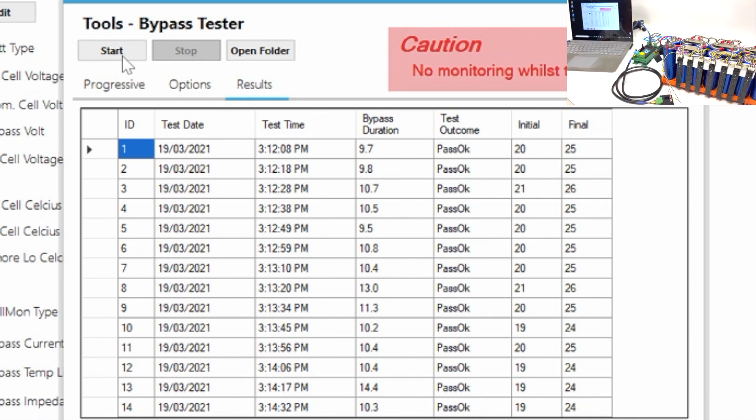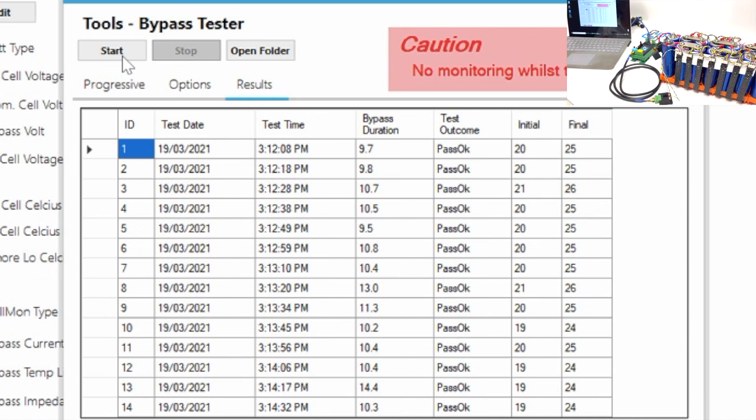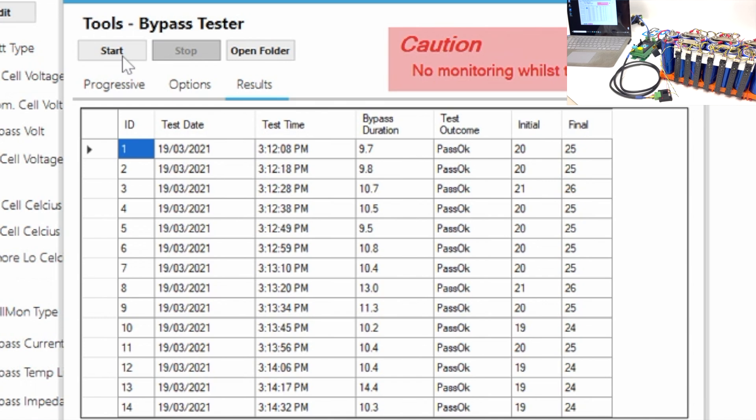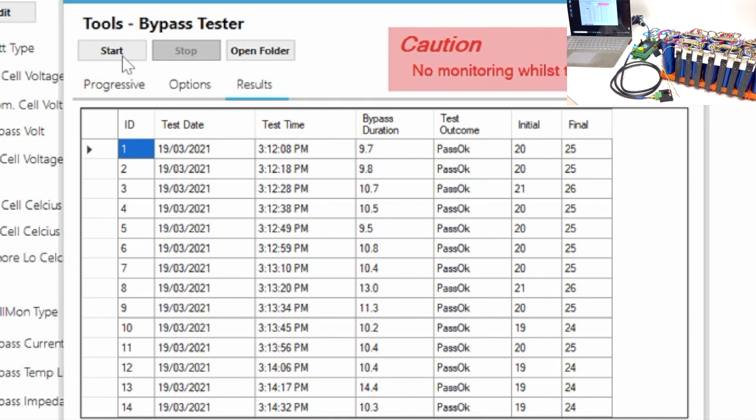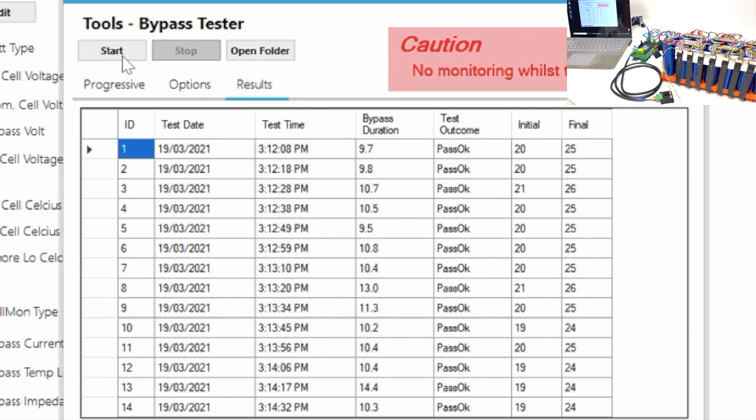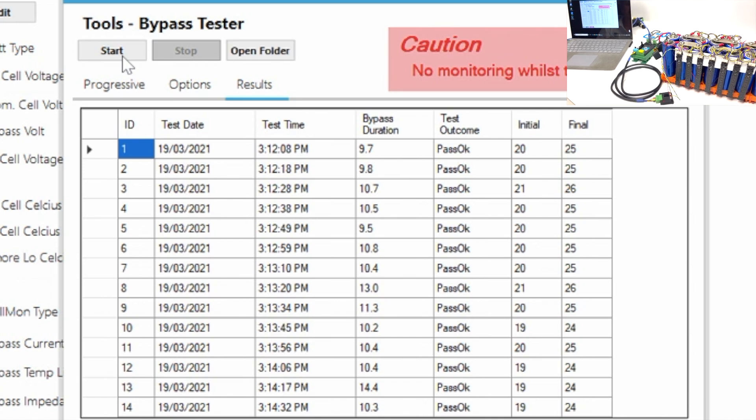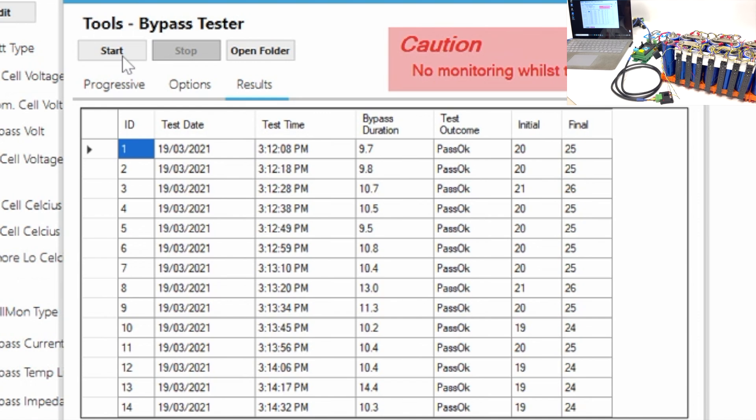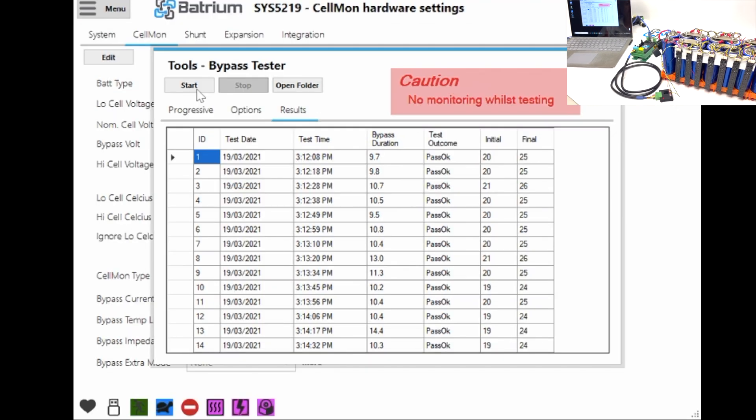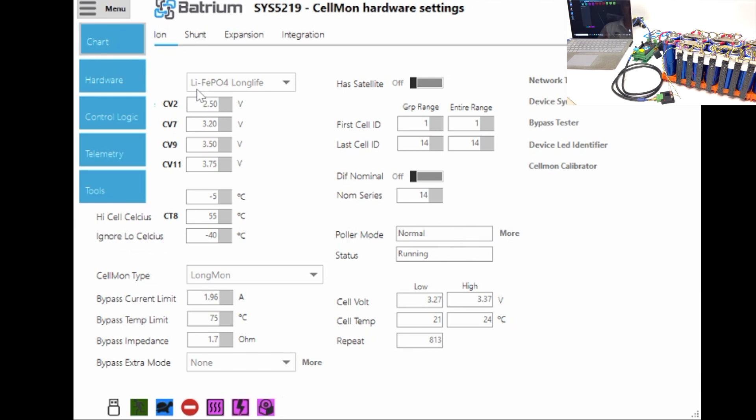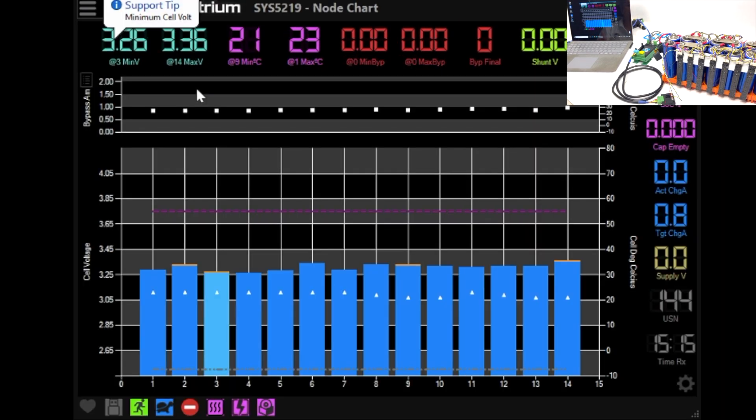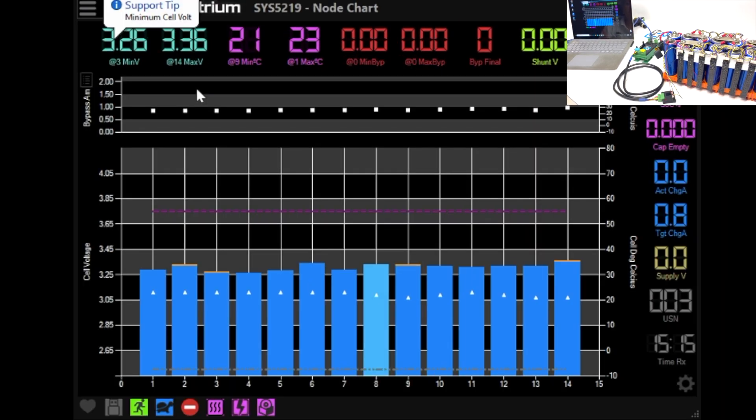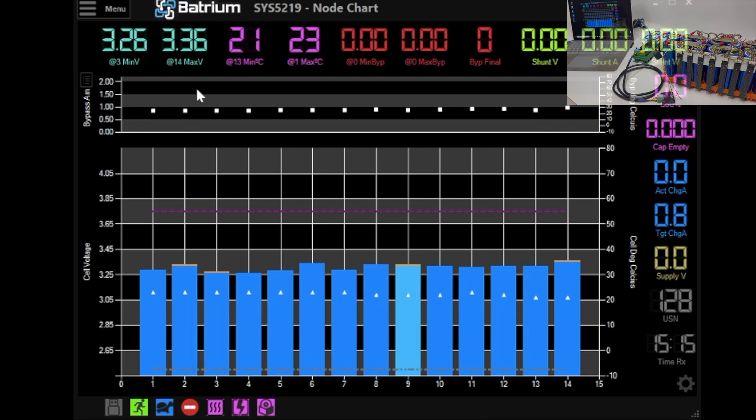So here we can see the outcomes and each one of them here has passed. That confirms that each cell cabling loom is working, the cell monitors are working and they're monitoring happily. So let's now close that window. All this data is stored in the report which is available in a folder that you can have a look at at a later point or send it through to us if there's some sort of issue that you can't follow.